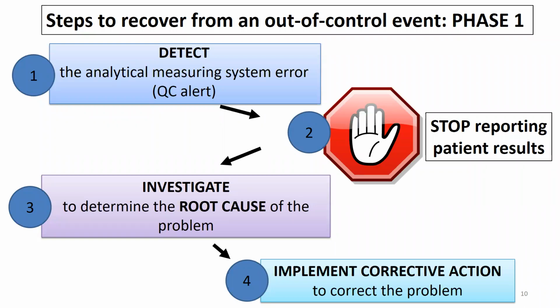The next step is to perform an investigation to determine the root cause of the problem. The root cause is the actual reason for the presence of the analytical measurement system issue. So oftentimes a problem is initially identified, but it's actually not the root cause. For example, QC may fail due to calibration drift, and that issue is corrected by recalibration, but that's not the real problem. It's only signaling an underlying problem. Perhaps the routine calibration frequency is inadequate for the stability of the reagent, or maintenance is not being performed frequently enough and the instrument is becoming contaminated. So it's really important to determine the actual root cause so that that cause can be directly addressed through corrective and preventative actions. Then the fourth step is to implement corrective action to correct the problem so that testing can get back up and running as quickly as possible.